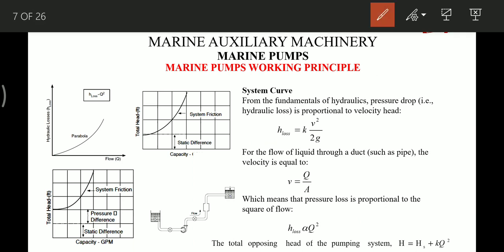Before studying the characteristic curve for pumps, let's look at system curves. Pumps cannot work in isolation — they are incorporated into a system containing piping, valves, flanges, and bends. The pump has to overcome all resistance in the system. System curves basically cover the pressure drop, which is proportional to the velocity head. Total head loss in the system follows from this relationship.